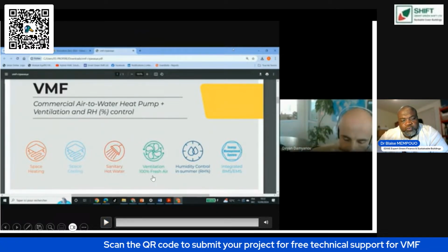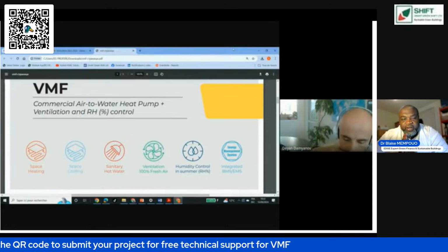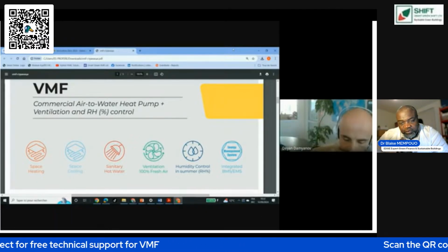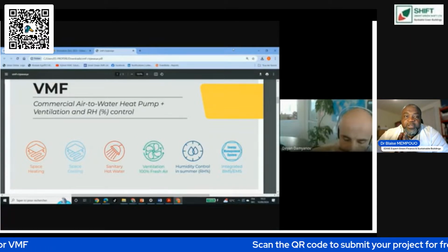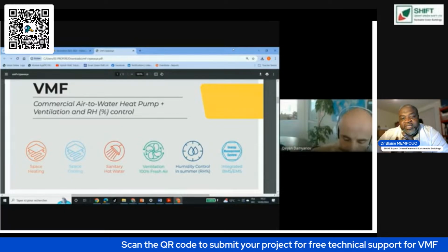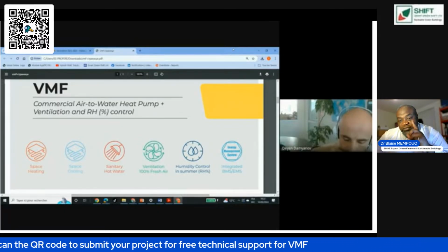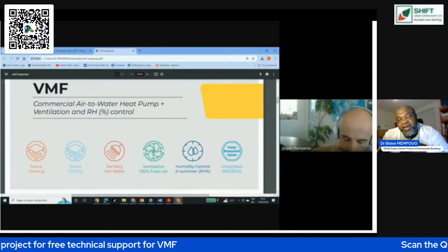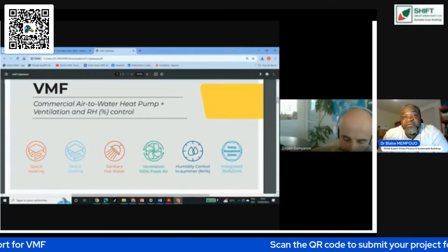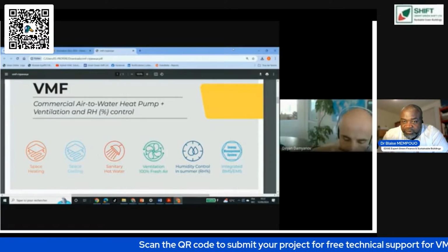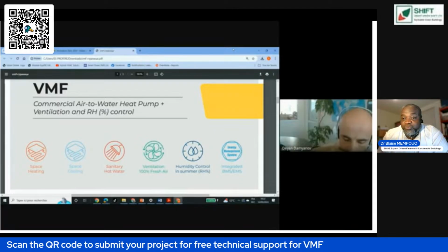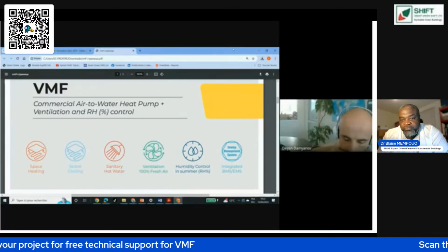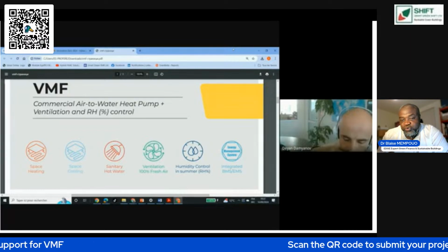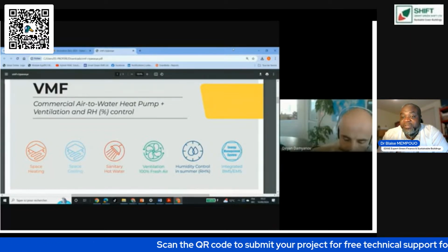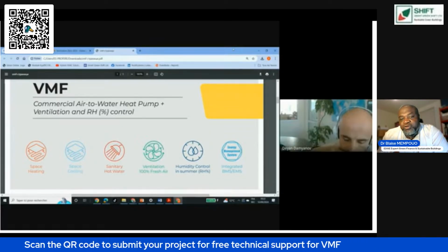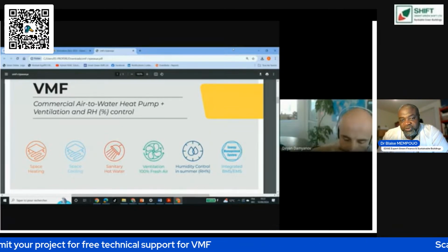So let's clarify here. When he said VMF - is VMF a VRV or VRF according to certain manufacturers? Yes and no. Yes, because it has a variable refrigerant, but no, because VRV or VRF most of the time have refrigerant everywhere - you have refrigerant outside in it and inside the building. That's why it's yes and no. Yes, because there's a variable refrigerant flow going in our system, and the compressor is variable also - a variable refrigerant - but it stays completely outside the building. Then no, because the refrigerant doesn't go all through the building, so it becomes yes and no.